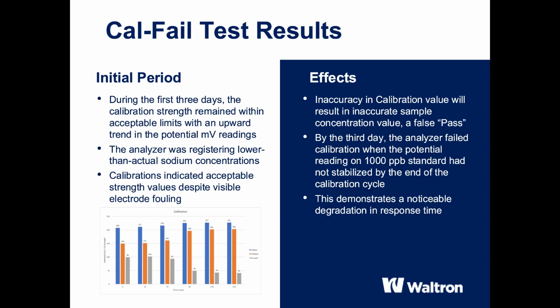At the same time, however, we are already seeing a clear upward trend in the millivolt readings for both calibration standards, the blue and orange bars. This is a clear indication of reference electrode drift caused by the incipient contamination. The dangerous effect of this is that the analyzer begins to report lower concentrations than actually present. It issues a false cal pass. The calibration is considered successful, even though the measurement is already inaccurate.